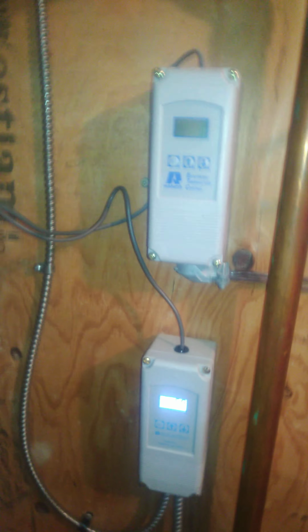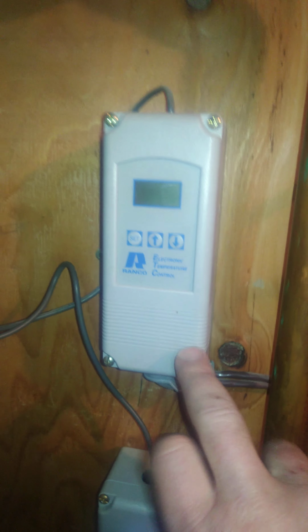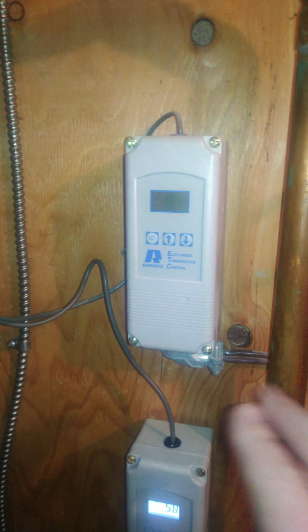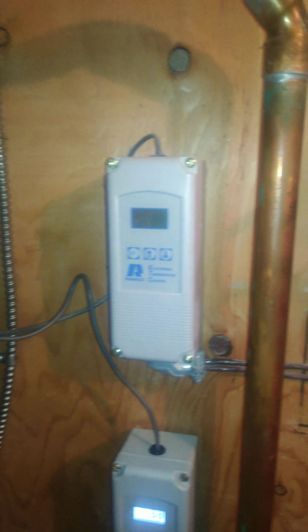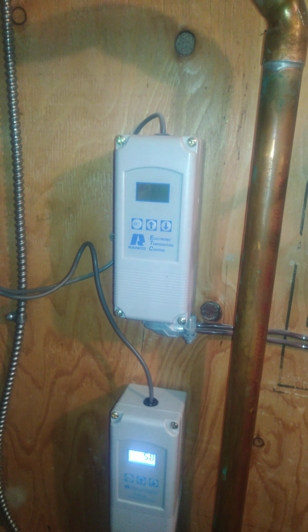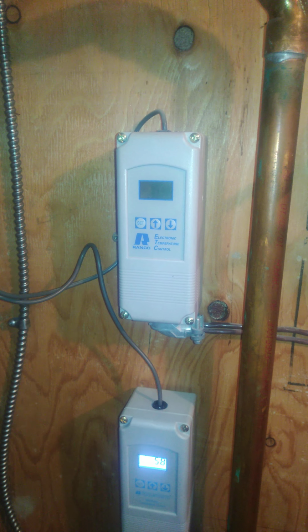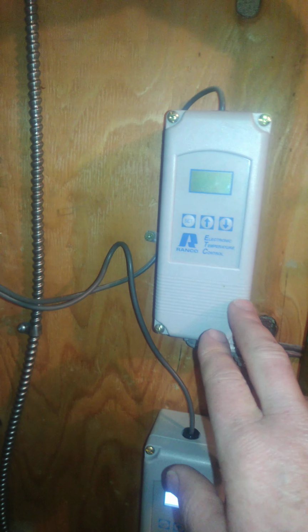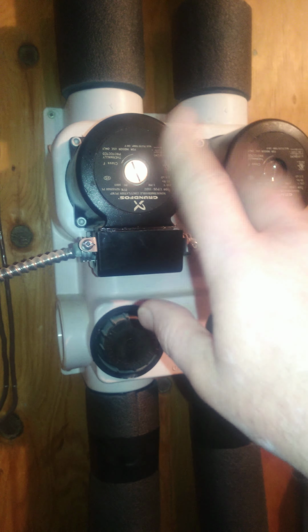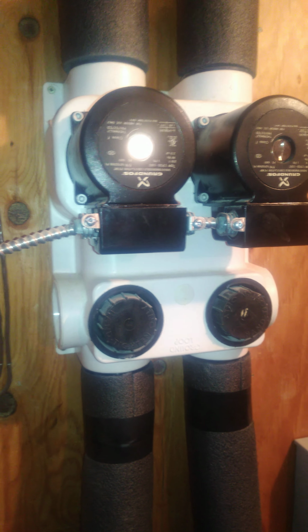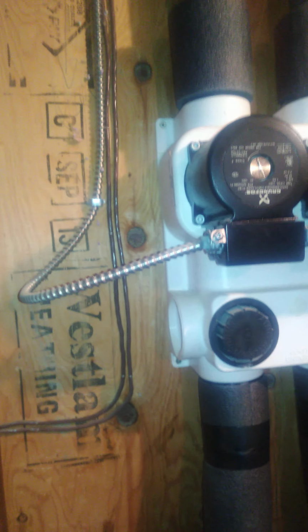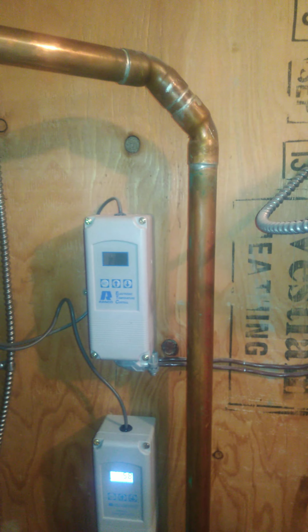Now you can't see this because I haven't got it on right now, but this aquastat for the Geo... getting ahead of myself here. It's set to bring the water in from the ground loop at about 50-some degrees, I'd say 45 to 50, because it's buried in the ground about 6 to 8 feet, and it's in heavy clay here, so we get excellent conductivity through the pipe. So it brings it in at 50-some degrees, and goes into the actual geothermal unit.